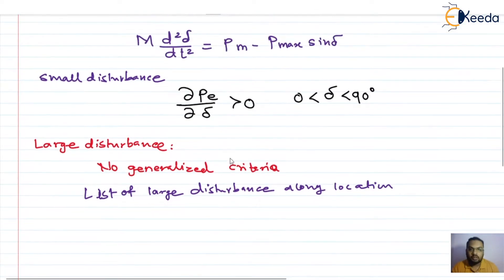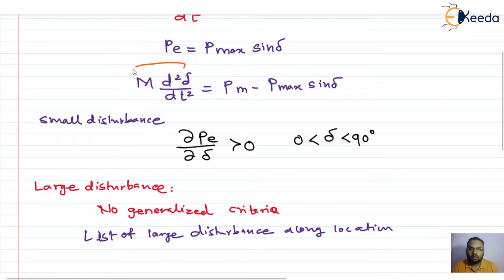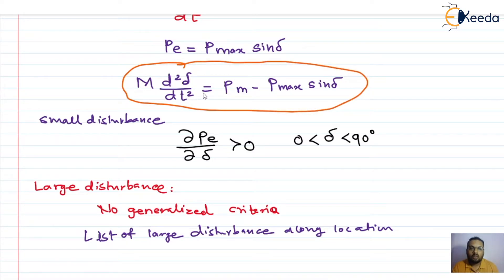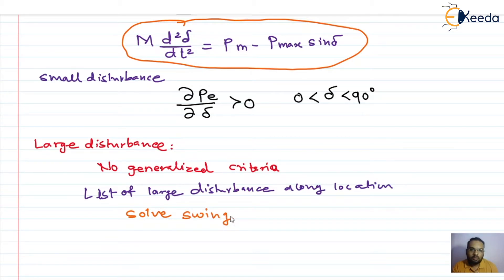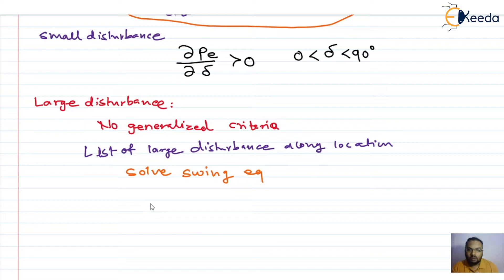Once you have the list, the next step is to solve the swing equation, which is a nonlinear differential equation, for a particular disturbance. Take any disturbance from the list and for that condition solve the swing equation. You have to take the help of a numerical technique to solve this nonlinear differential equation. After solving, a graph of rotor angle versus time — the swing curve — is plotted.